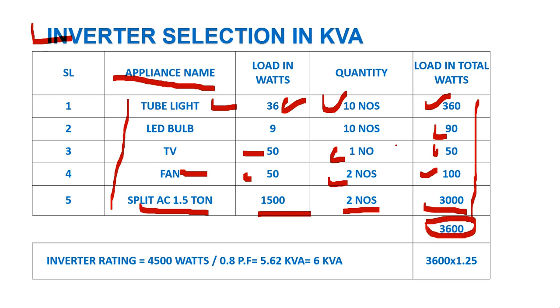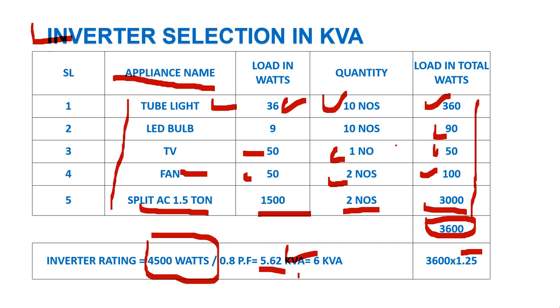Now add 20% extra for future load expansion, which brings the total to approximately 4320 watts. After considering the power factor, the total comes to around 5620 VA. Dividing by 1000 gives 5.62 kVA — so you round up and purchase a 6 kVA inverter from the market. That is how you select the correct inverter rating for this load.